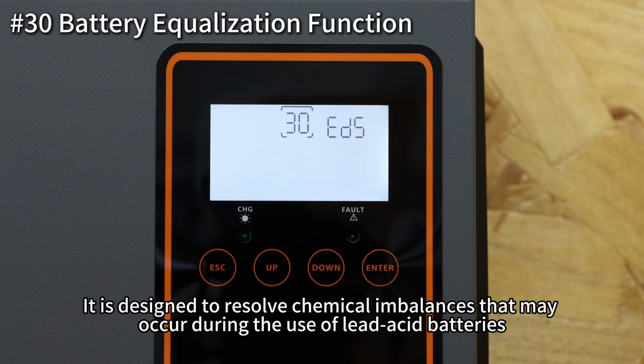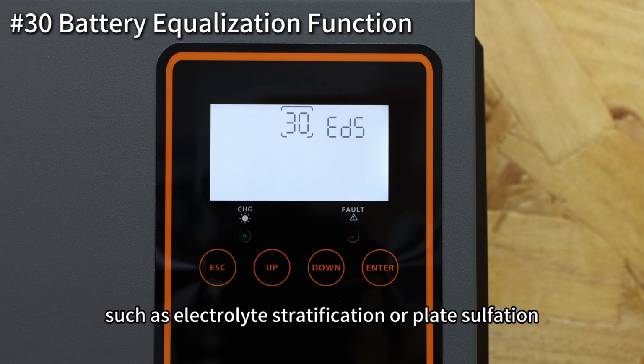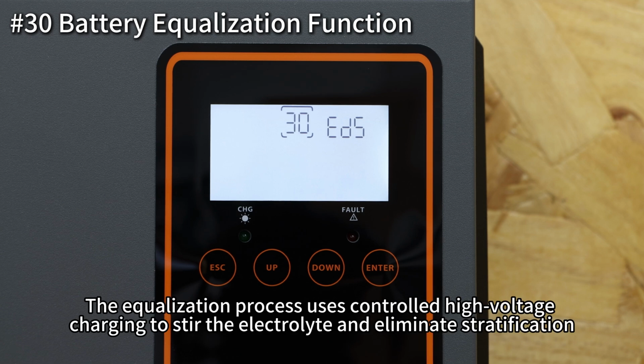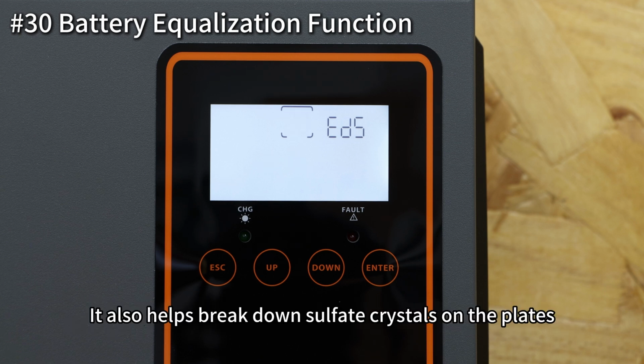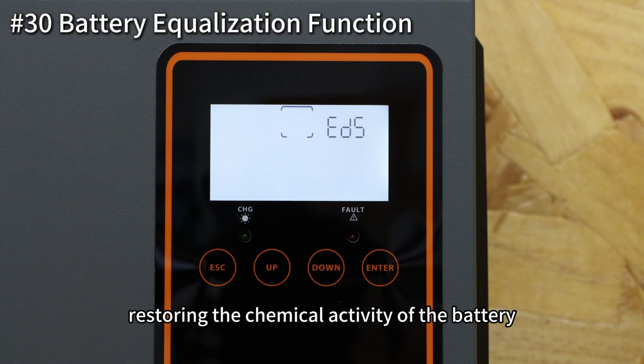It is designed to resolve chemical imbalances that may occur during the use of lead-acid batteries, such as electrolyte stratification or plate sulfation. The equalization process uses controlled high voltage charging to stir the electrolyte and eliminate stratification. It also helps break down sulfate crystals on the plates, restoring the chemical activity of the battery.